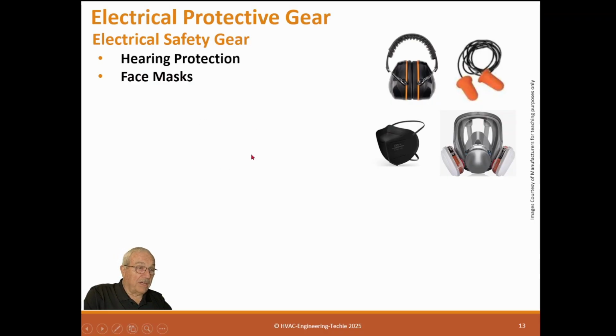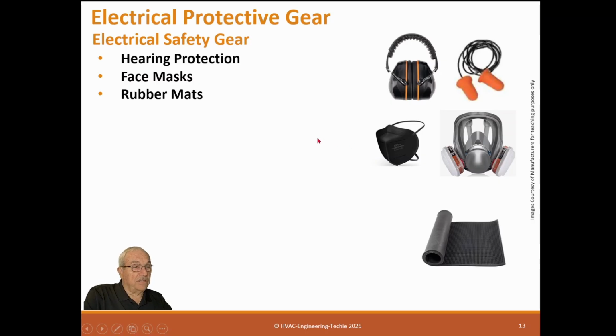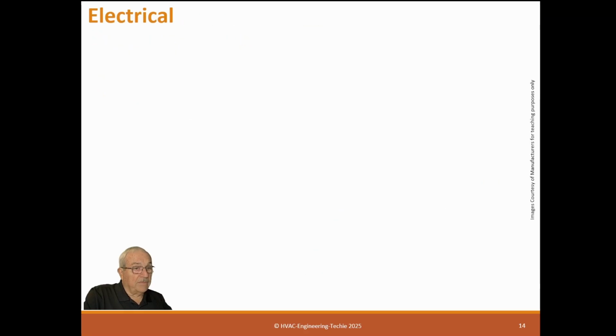You don't need it for the electrical part unless there's an arc flash, and it would be really nice to have one to keep from getting the contamination from the explosion into your lungs. Rubber mats are designed to put down before you work on a gear to isolate you from the ground. Man hooks are designed for your partner to have in case you get hooked up. He can jerk you off, because when you get hooked up to an electrical arc or electrical short, it won't let you loose. You can't get loose because it's control of your nervous system. You no longer have control of that. So that's what the hook is for: your partner grabs you and jerks you away from that.